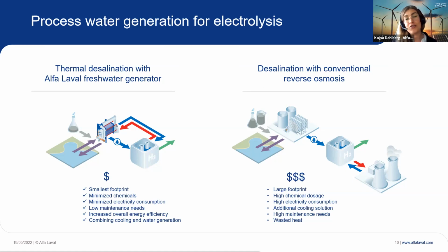So an alternative is to use thermal desalination technology, where the water is demineralized to the quality needed using the waste heat. This process evaporates the water under vacuum pressure, meaning it can operate at the low temperature found in the electrolyzer. So we get a solution that combines both the cooling solution and water generation in one step. You minimize chemical and electricity consumption significantly, and overall the process gains around 27% efficiency in green hydrogen production, considering the electrolyzer and water production together.